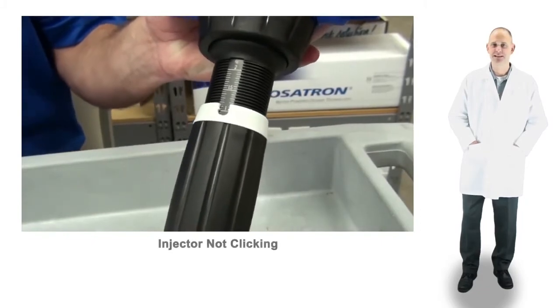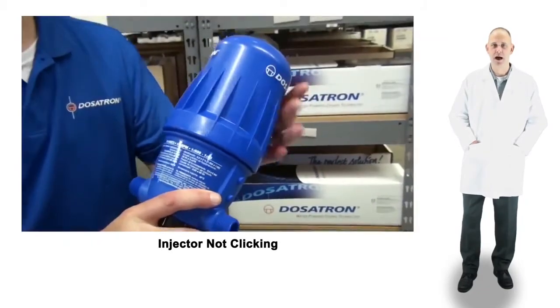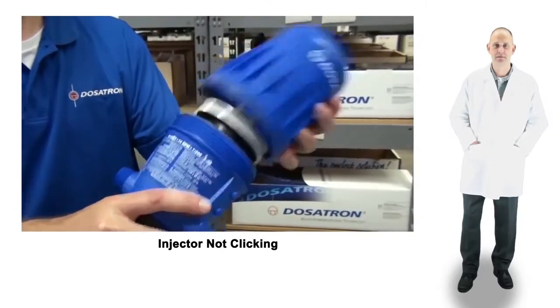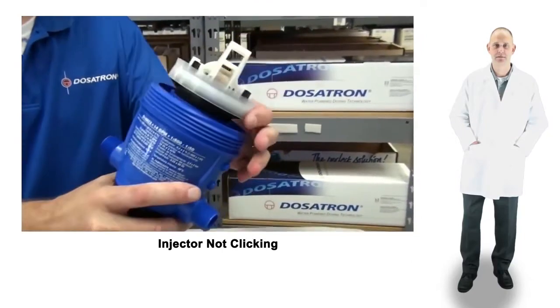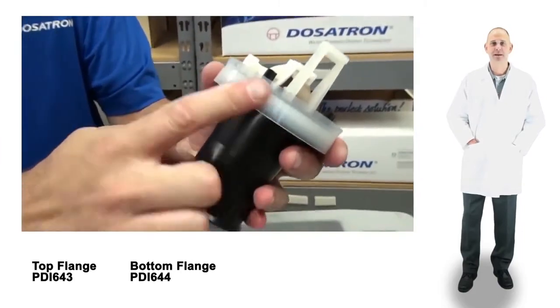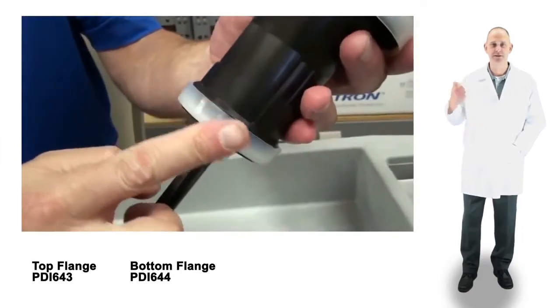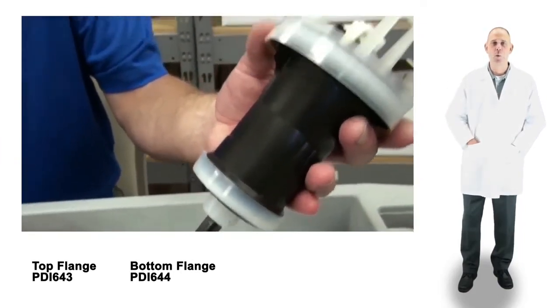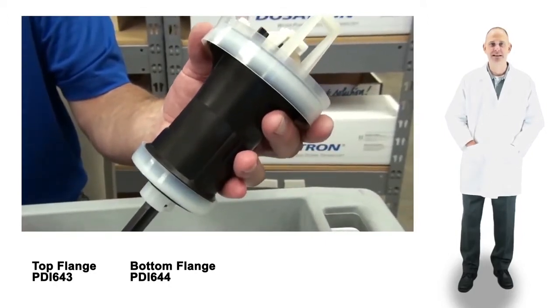If the injector isn't clicking, remove the blue bell housing and pull the piston straight out. Visually inspect the upper and lower white flanges on the piston shell. If they are worn or have scratches, the flanges need to be replaced.